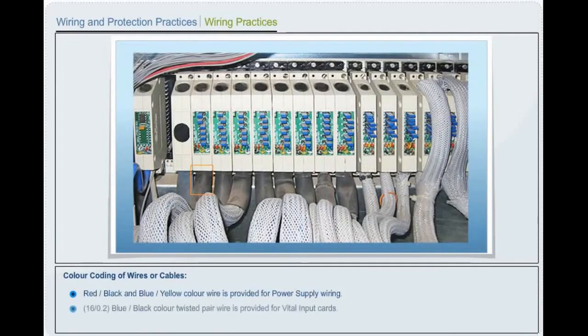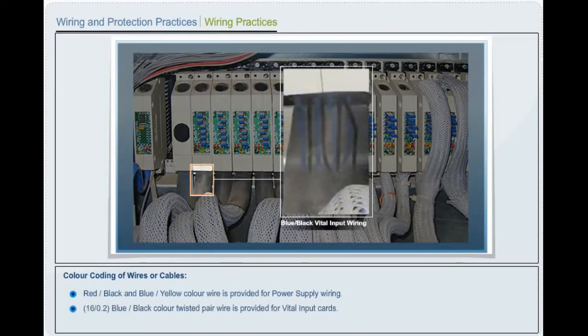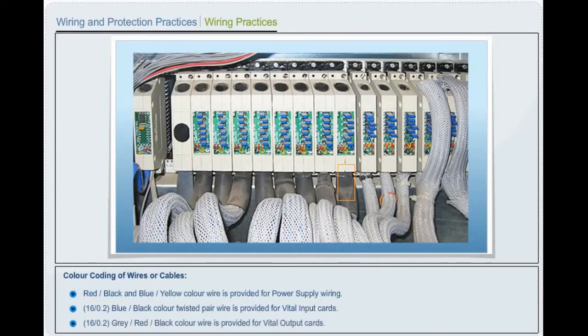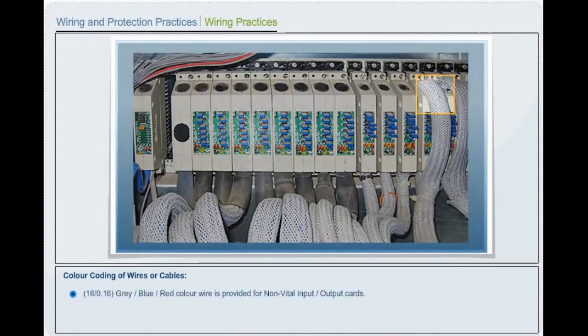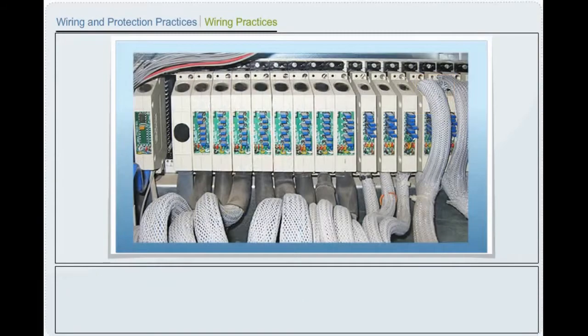Red and black or blue and yellow color wires are provided for power supply wiring. 16 by 0.2 mm blue or black color twisted pair wire is provided for vital input cards. 16 by 0.2 mm gray, red and black color wires is provided for vital output cards. 16 by 0.16 mm gray or blue or red color wire is provided for non-vital input or output cards.